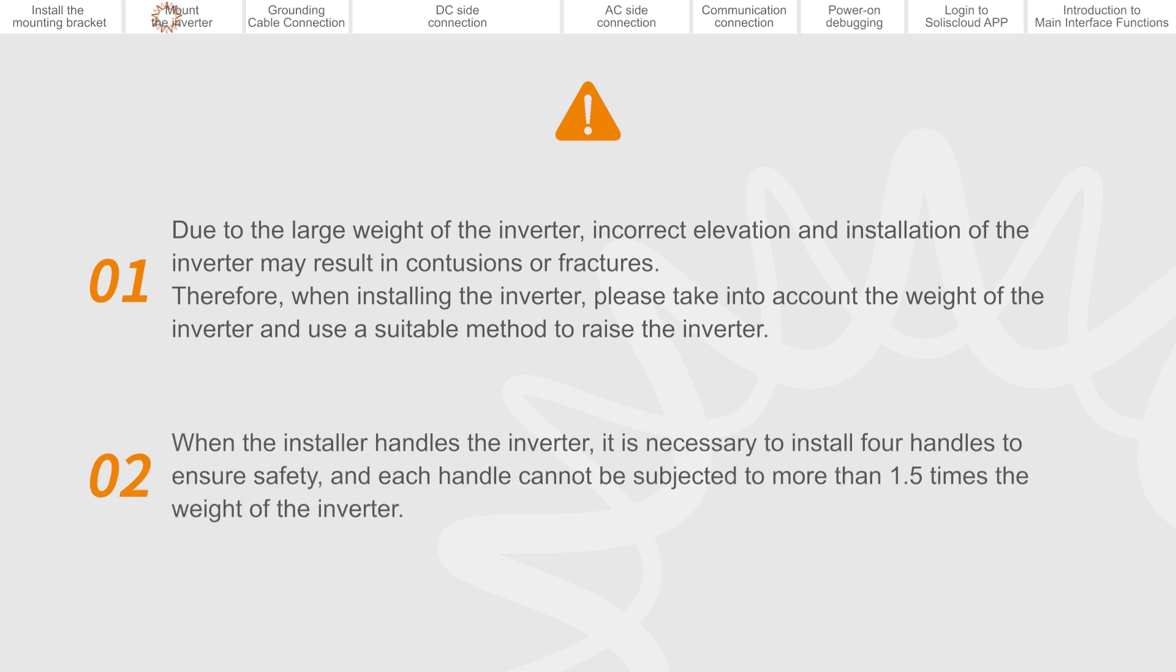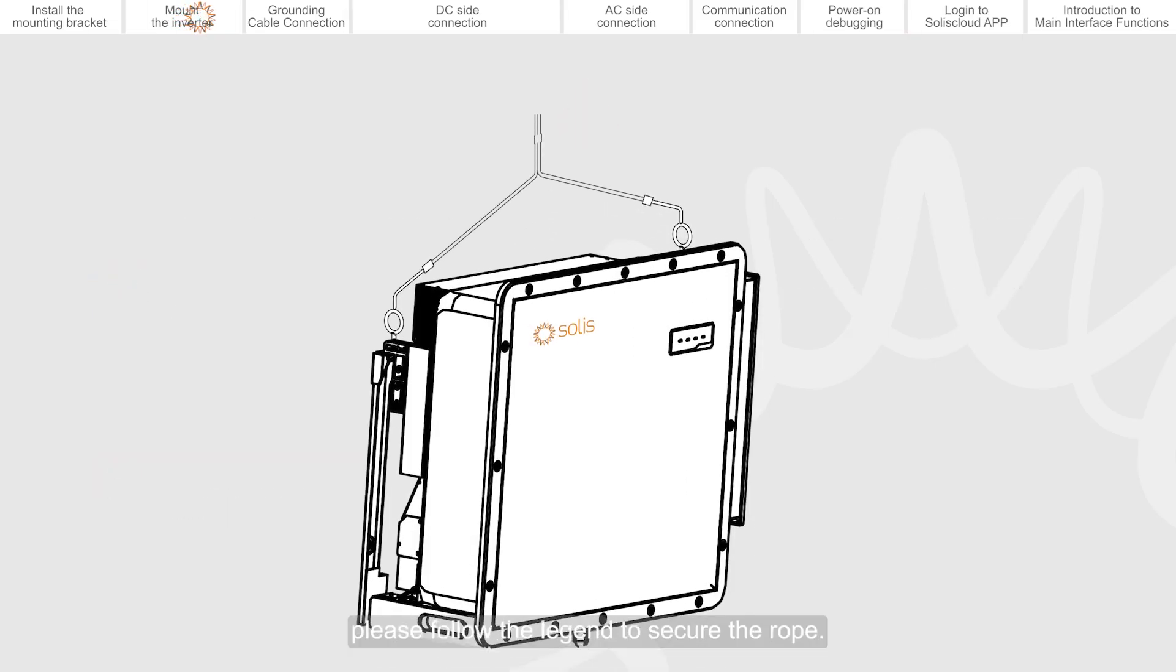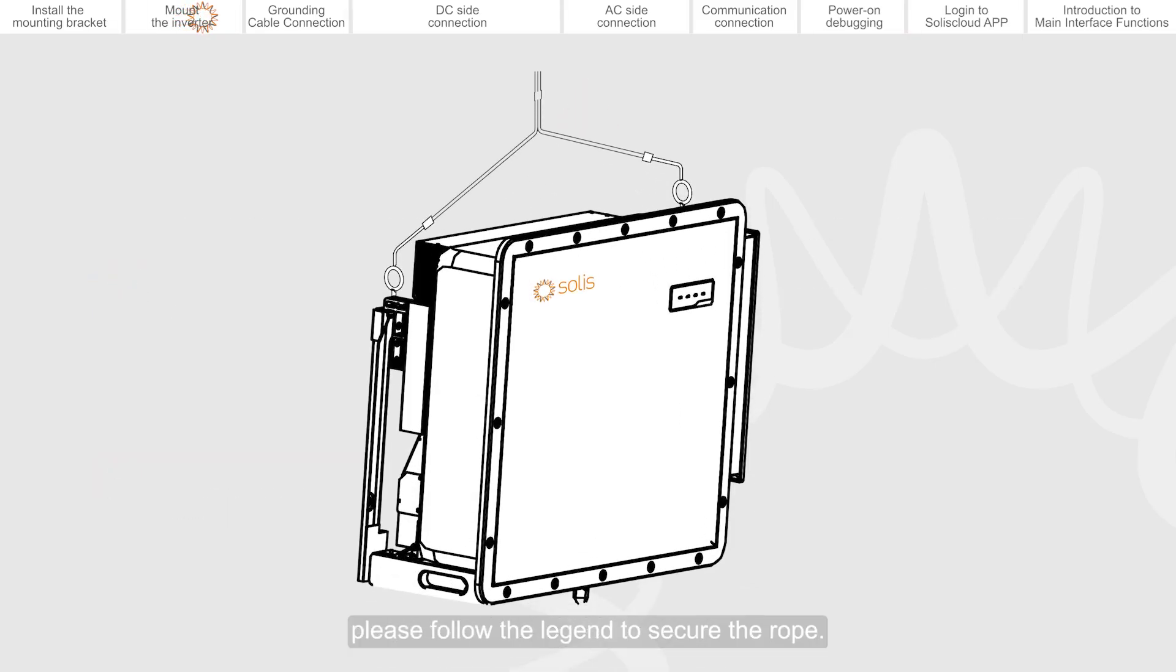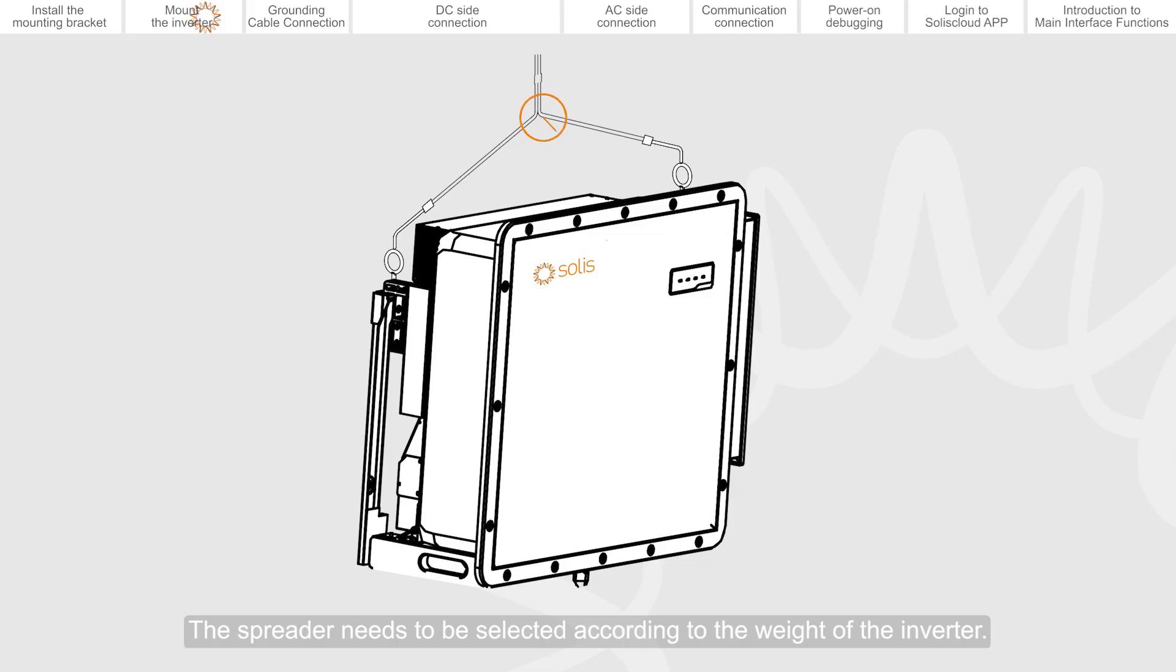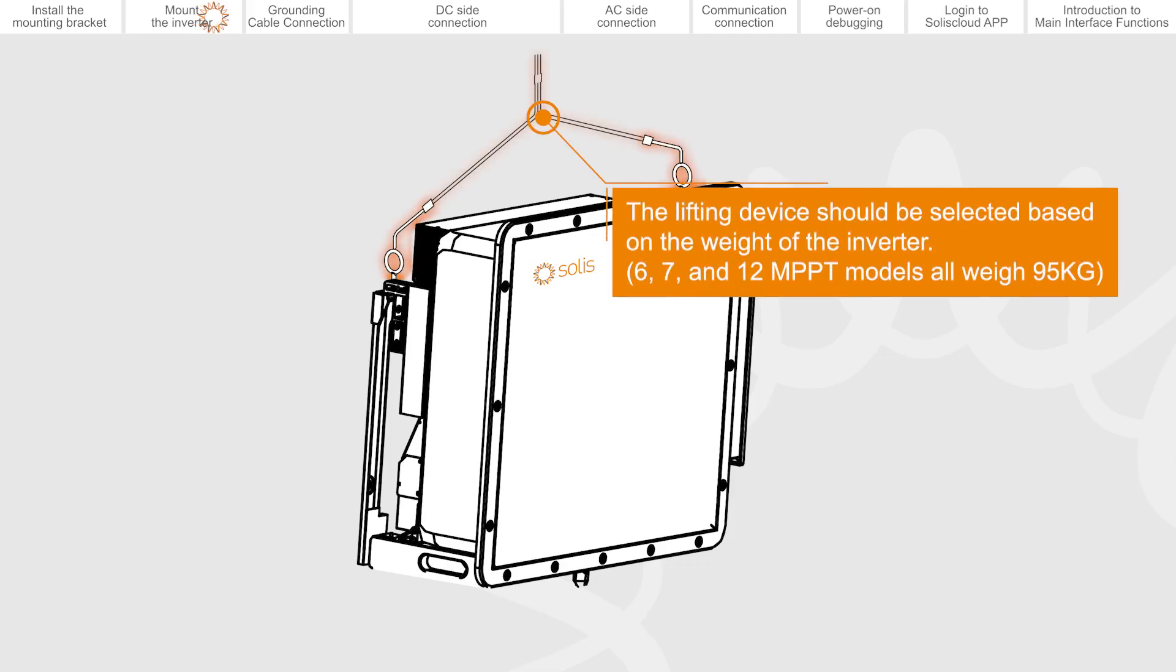When the installer handles the inverter, it is necessary to install four handles to ensure safety, and each handle cannot be subjected to more than 1.5 times the weight of the inverter. If hoisting is required, please follow the legend to secure the rope. The spreader needs to be selected according to the weight of the inverter.